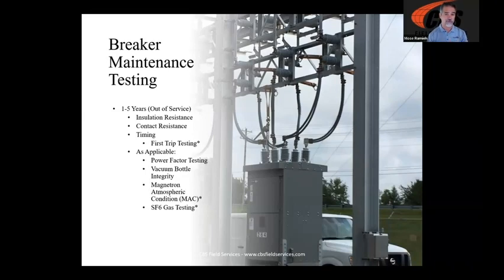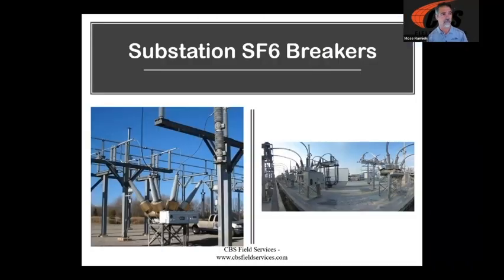Timing. I'm going to talk about first trip timing, which I think is a test that is underutilized. We can also power factor our breakers, do vacuum bottle integrity tests for our vacuum breakers, but there's a better test maybe called the magnetron atmospheric condition test, or the MAC test for short, because that's a mouthful. And then finally, SF6 breakers. I got some ideas on SF6 breakers for our audience today as well. And that's where I'm going to start. Let's talk about SF6 breakers.